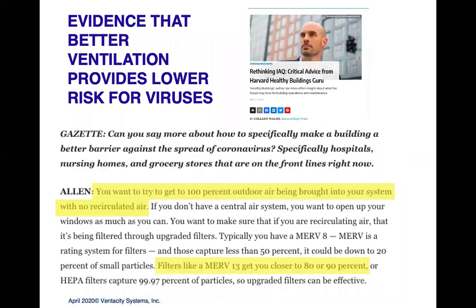A lot's coming out with COVID-19 about how we can look at HVAC systems and improve buildings' health. This is from a gentleman at Harvard School of Public Health who wrote about this, and there are two takeaways. One is 100% outside air, dedicated outdoor air systems, and no recirculated air. RTUs typically, and I'm going to expand on this, recirculate to heat and cool air and open a damper to provide fresh air. And they are recirculating, and that is just common sense, as that could be a real problem. The other thing is a MERV 13 filter to get close to 80 to 90% of all things coming in.